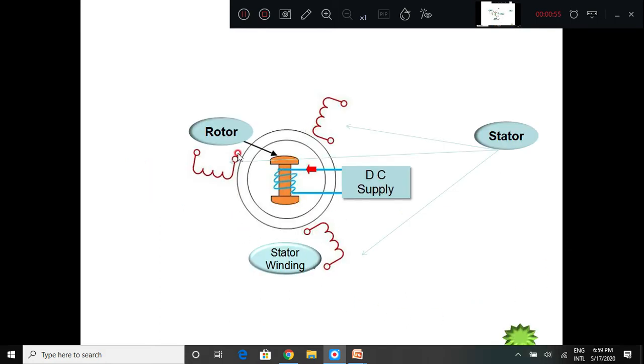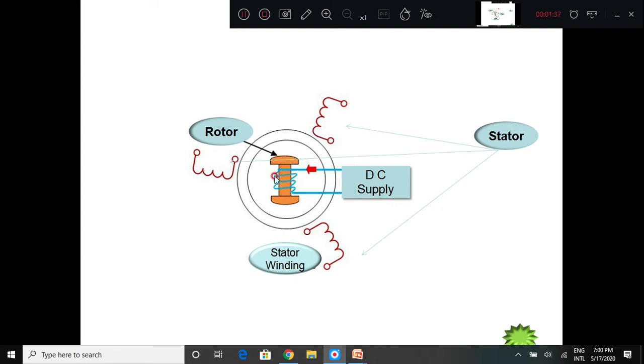There are two main parts. One is the stator, which has armature conductors or armature winding - known for three different windings R, Y, and B because it is a three-phase generator. The second part is the rotor, which is a rotating part. In the case of the alternator, the rotor is the magnetic field system. To create the magnetic flux, the rotor is excited by DC supply. The rotor consists of electromagnets with a field winding, and external DC supply is given to the field winding to create the magnetic flux.